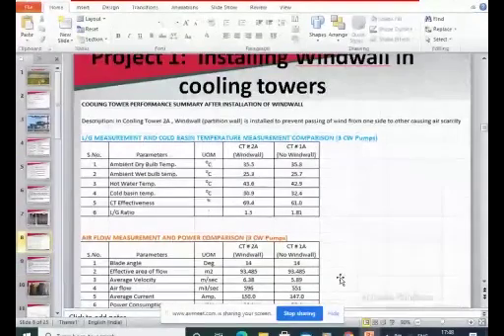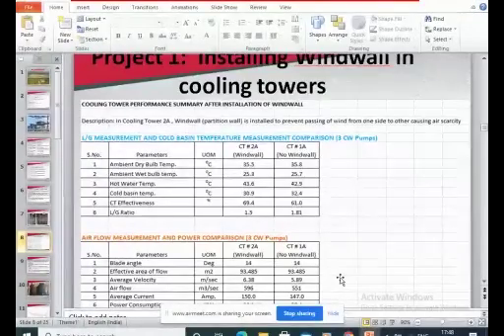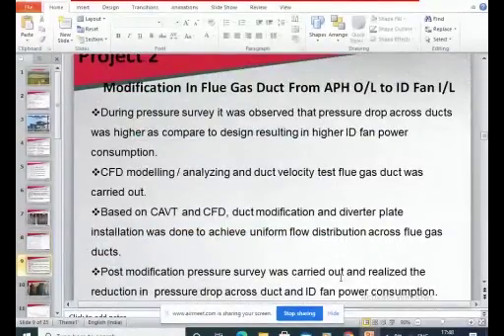Okay, so we completed project 1 for installing the wind wall in the cooling towers. The second project that we took is flue gas duct modification from the air preheater to the ID fan inlet. The study first found that there was a pressure drop across the duct from the air preheater to the ID fan, and the design values were showing something and the actual values something else. So we identified the area where this actual pressure drop is, and there was also a problem of flue gas distribution in the duct.